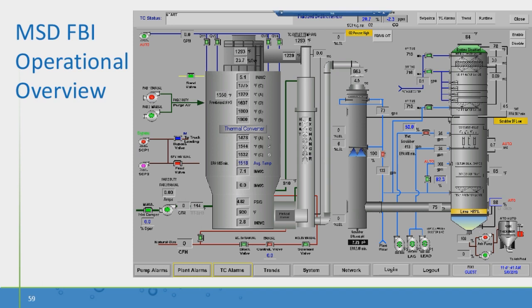It goes from 1239 degrees at the top of the heat exchanger down to 663 degrees before going into the quench right here, where we inject water into the airstream and keep moving down, and it's at 75 degrees here. Granted, this is at the incinerator's resting state, before it goes into the actual scrubber system with the Sorbent Polymer Composite trays. We also monitor all of our water flows through this screen, and we do use reclaimed plant water from our facility to save significantly on city water, economically and environmentally as well.